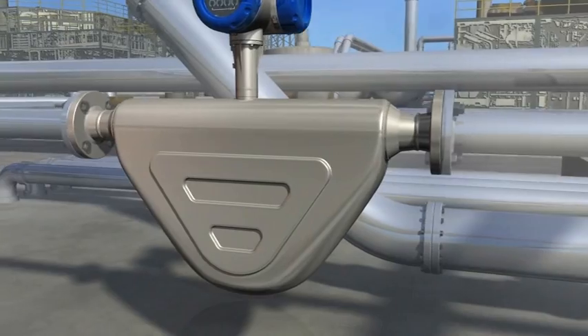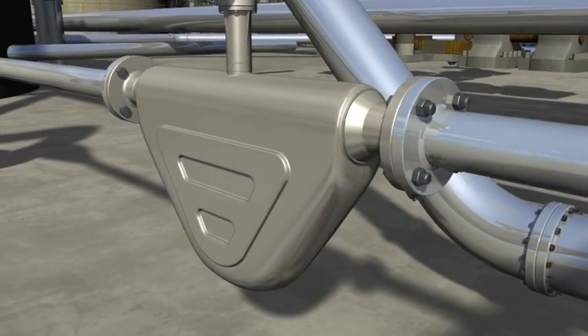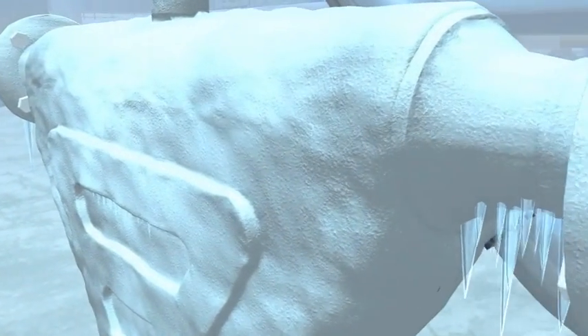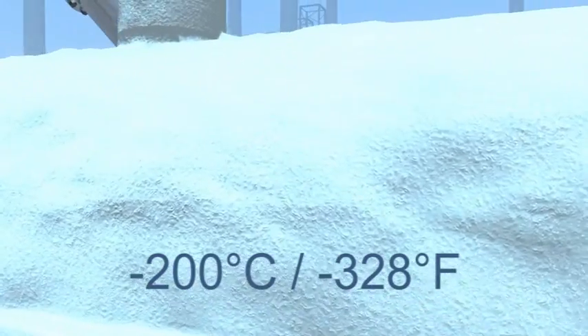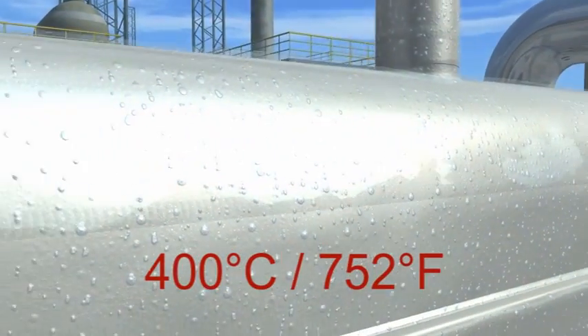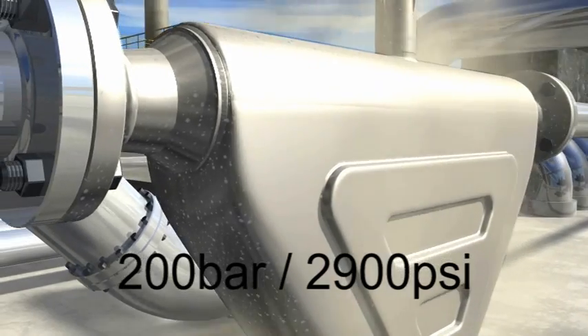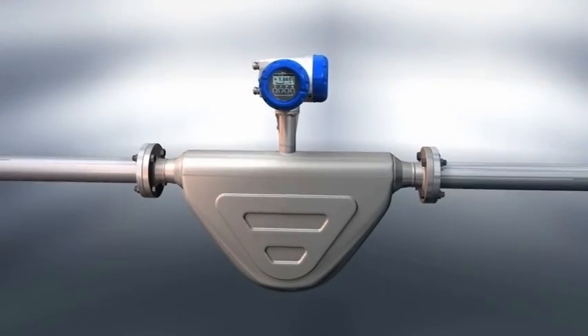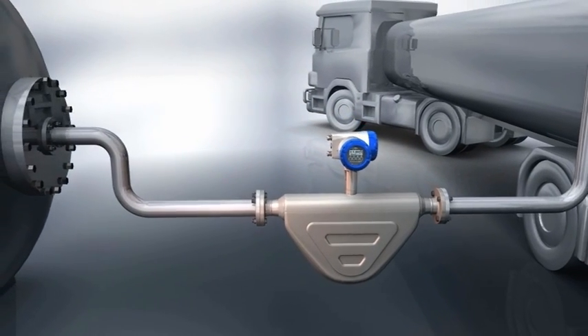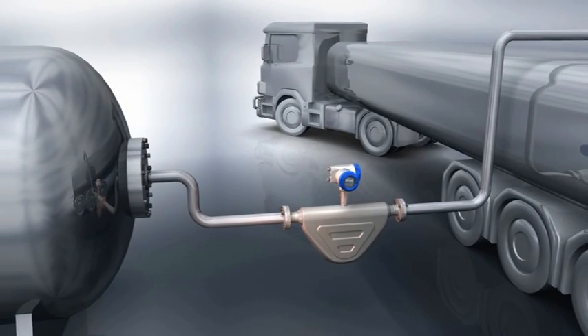Krohne's OptiMass 6000 is the twin bent tube meter designed as the new standard for high performance in the process industries. It can operate down to cryogenic temperatures as low as minus 200 degrees centigrade and up to 400 degrees centigrade, and at pressures of 200 bar. The 6000 is capable of both liquid and gas custody transfer according to OIML and MID, and complies with API and AGA guidelines.